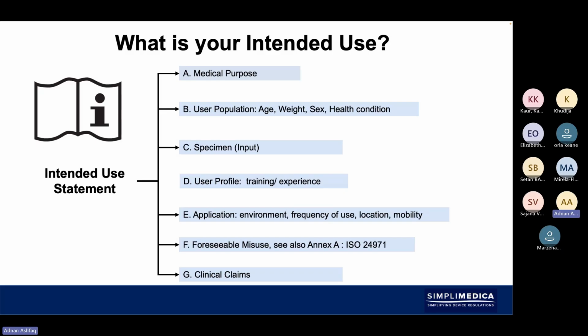And I call this an intended use statement because it's much broader than just the intended purpose. So we could have a look at the medical purpose, the user population, the age, the weight, the sex, the health condition, what specimens are required as input to the medical device to then give it the related output, what the user profile might be, what training is needed, what experience is needed. So this could be a layperson, could be home use, it could be a clinician in a clinical environment. So we look here at the application environment, the frequency of use. It might be a single-use medical device. It could be a device that's designed to be used multiple times. The location, if it needs to be in a specific location, if it needs to be installed, the mobility, if it's a portable device, is it handheld? All these factors constitute the intended use statement.